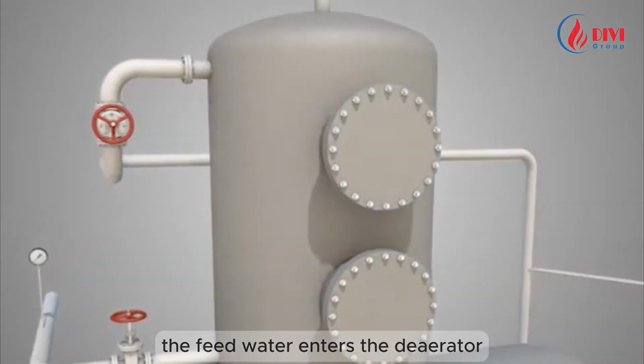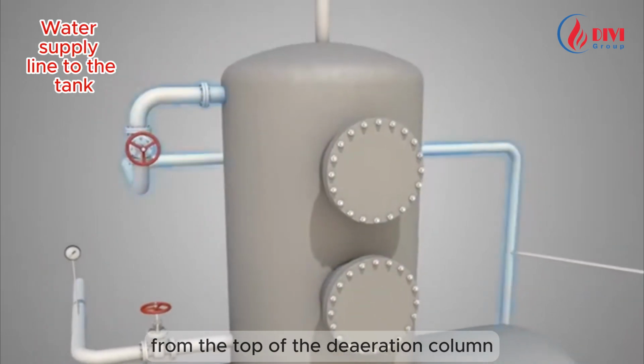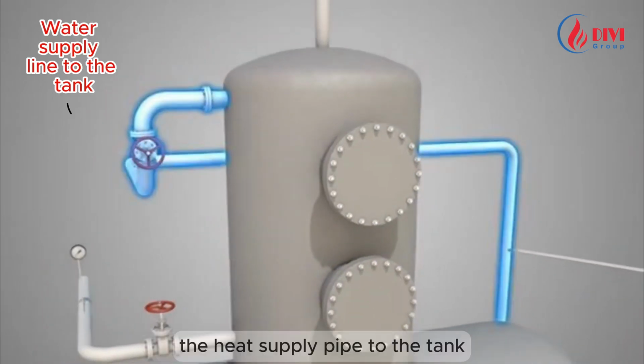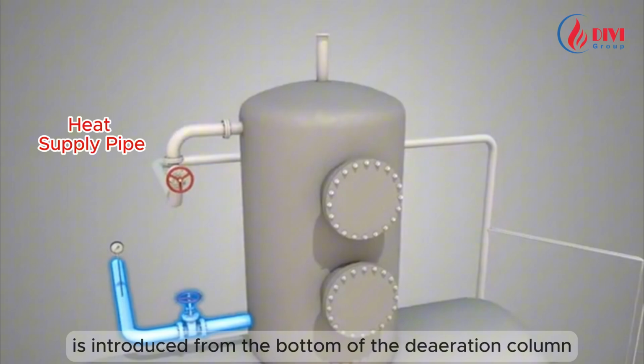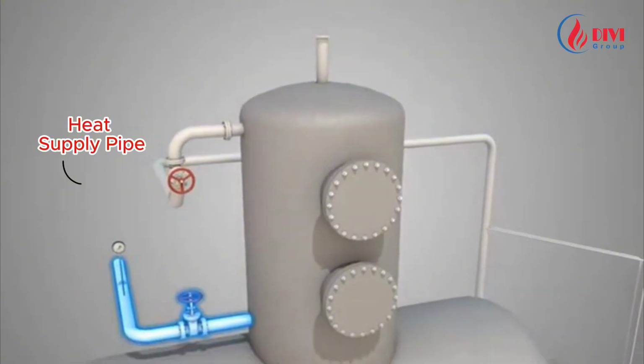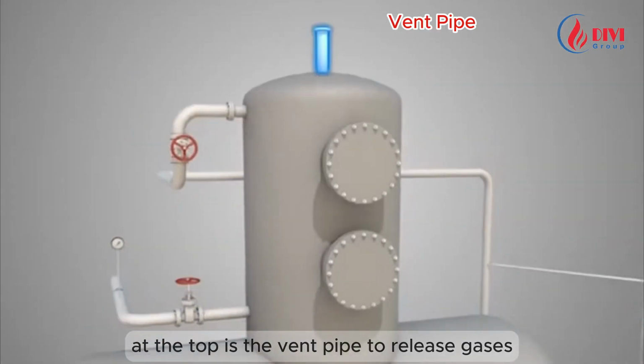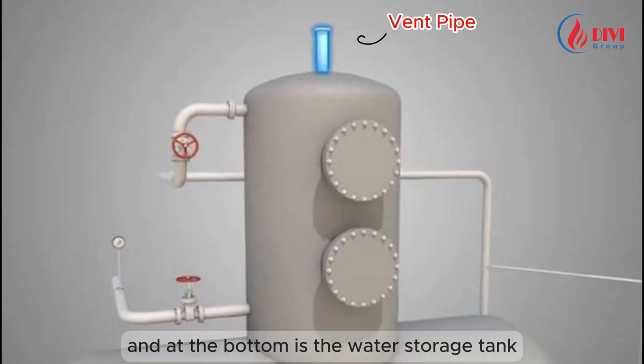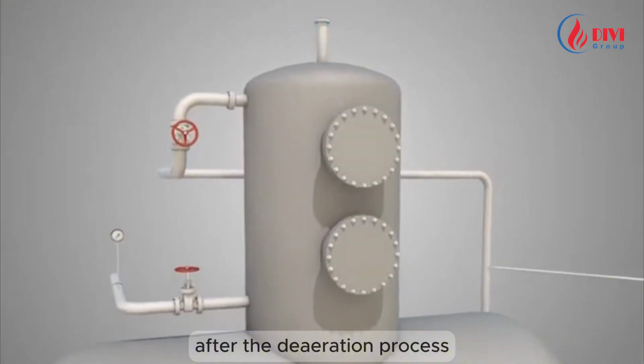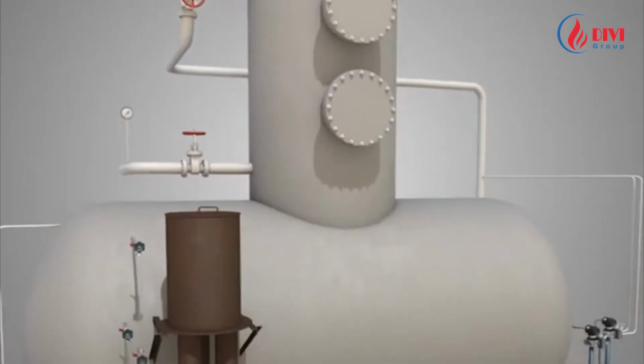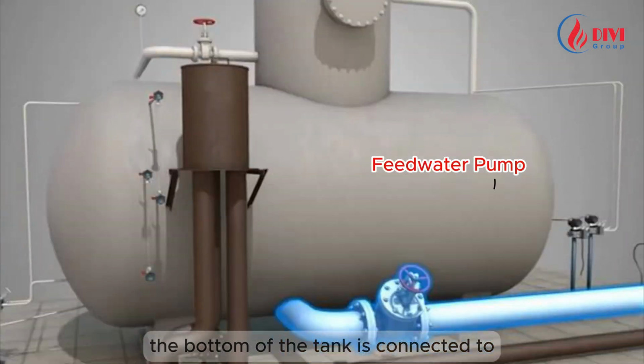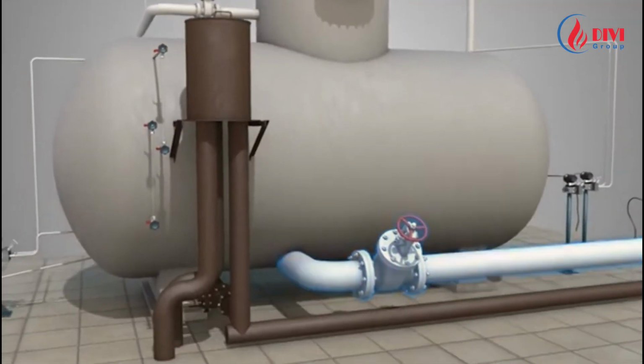The feed water enters the Deaerator from the top of the deaeration column. The heat supply pipe to the tank is introduced from the bottom of the deaeration column. At the top is the vent pipe to release gases, and at the bottom is the water storage tank after the deaeration process. The bottom of the tank is connected to the suction pipe of the feed water pump to supply water to the boiler.